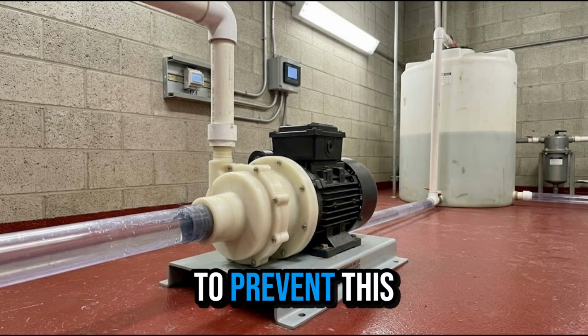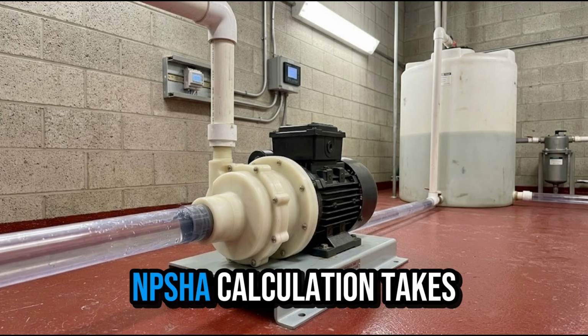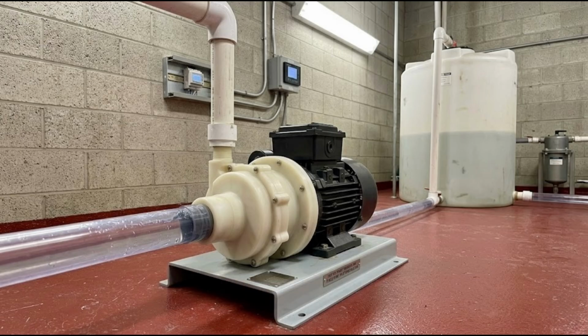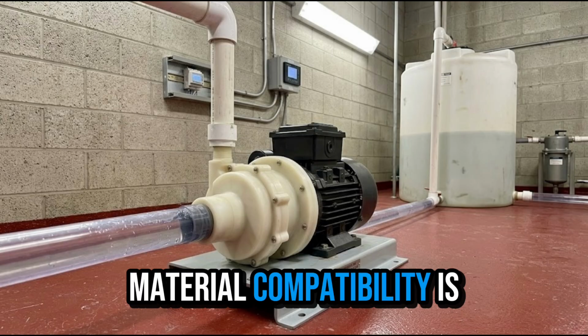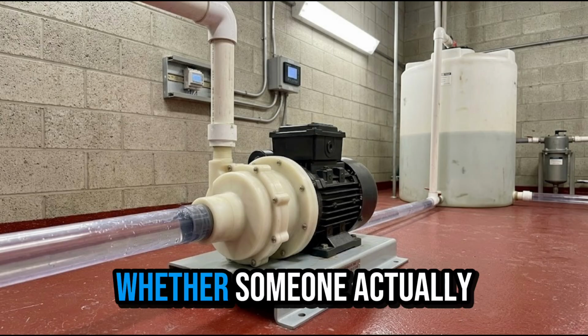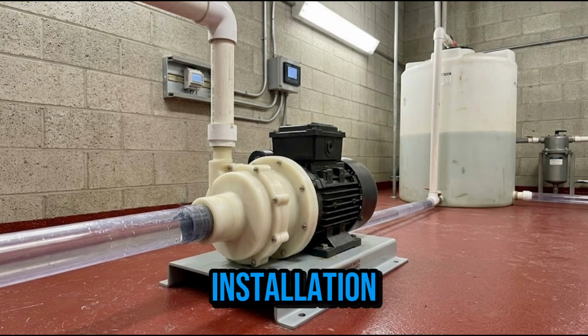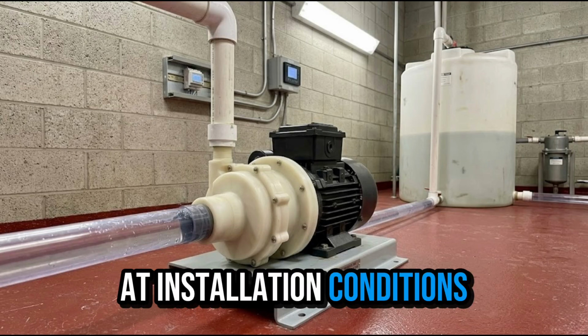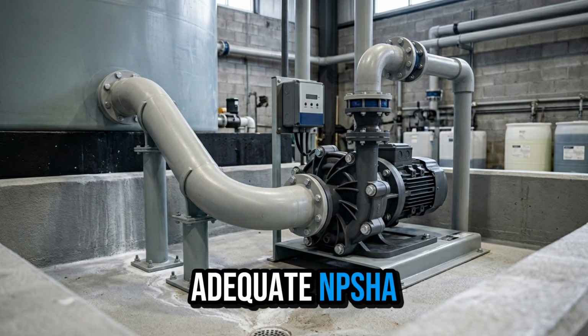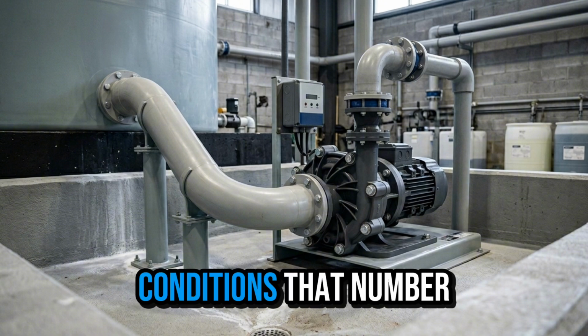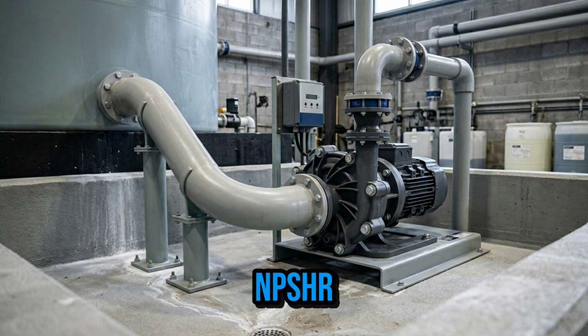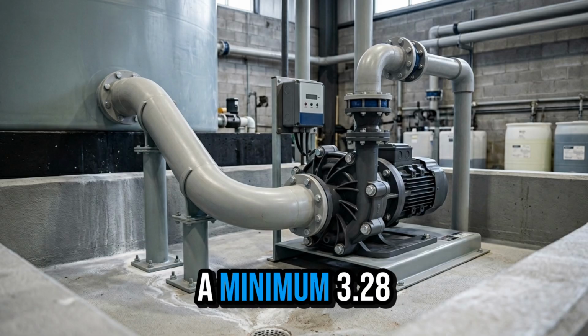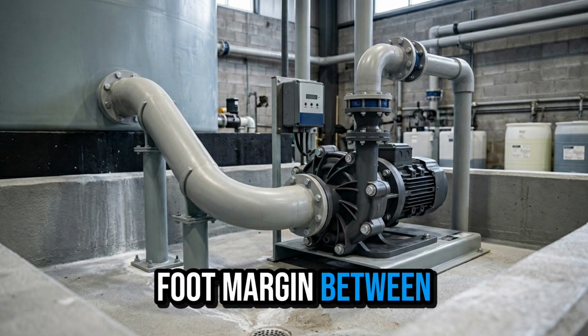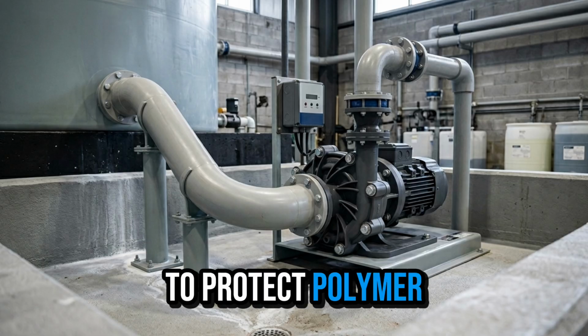The engineering required to prevent this is simple. NPSHa calculation takes minutes. Suction review takes minutes. Material compatibility is a look-up. The difference is whether someone actually does it before installation. If you calculate at installation conditions, you may show adequate NPSHa, but in real conditions, that number can drop below NPSHr in corrosive service. Liberty CES applies a minimum 3.28-foot margin between NPSHa and NPSHr to protect polymer components.